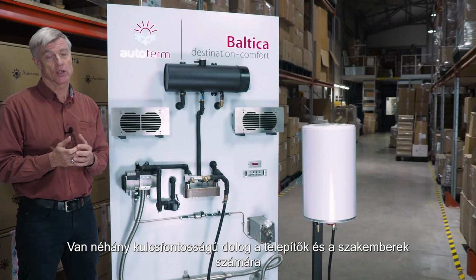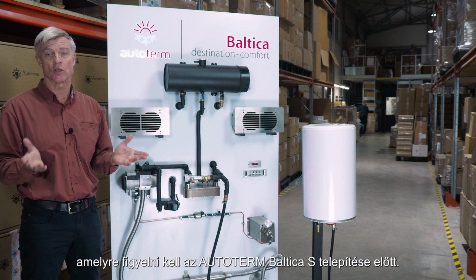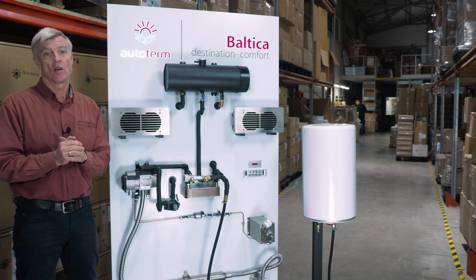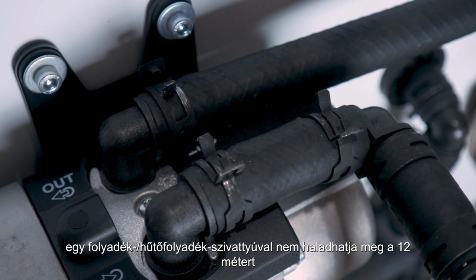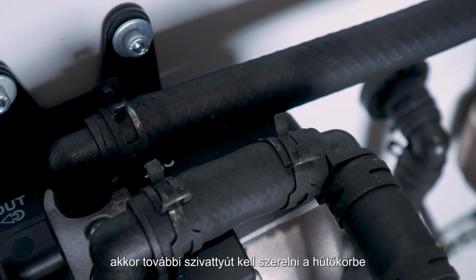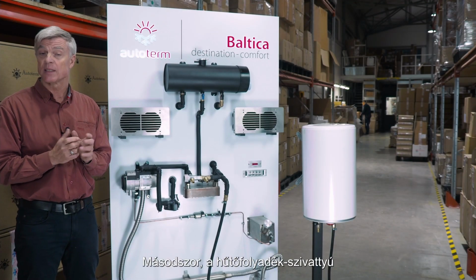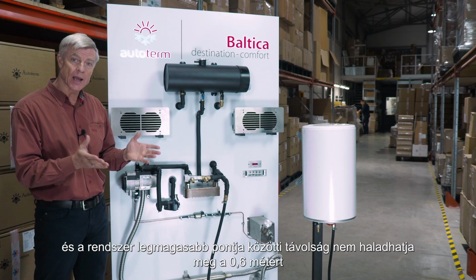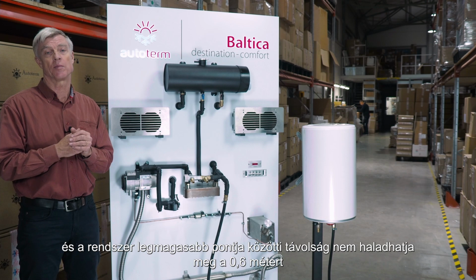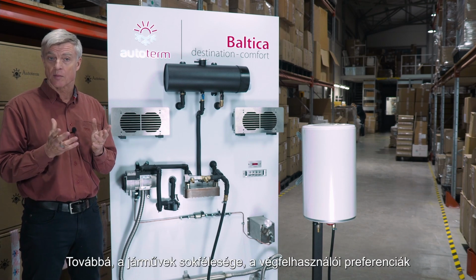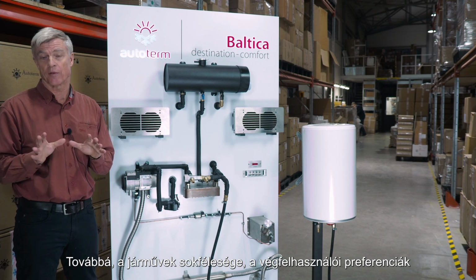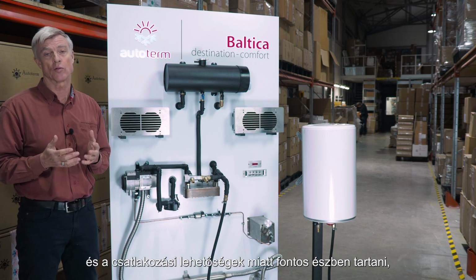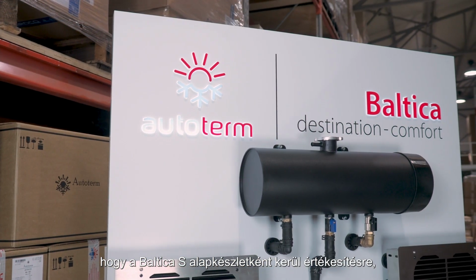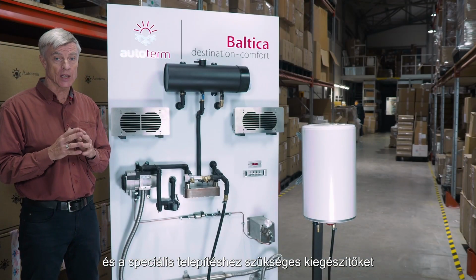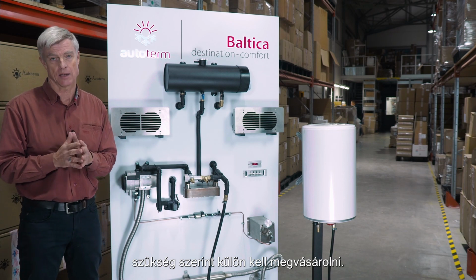There are some key things for installers and specialists to keep in mind before installing the AUTOTERM Baltica S. Firstly, the total coolant hose length with one liquid coolant pump cannot exceed 12 meters. If longer than 12 meters, another pump must be added to the loop. Secondly, the distance between the coolant pump and the highest point of the system cannot exceed 0.6 meters. Next, because of the variety of vehicles, end user preferences and connection options, it's important to remember that the Baltica S is sold as a basic kit, and additional items for specific installation must be purchased separately as needed.